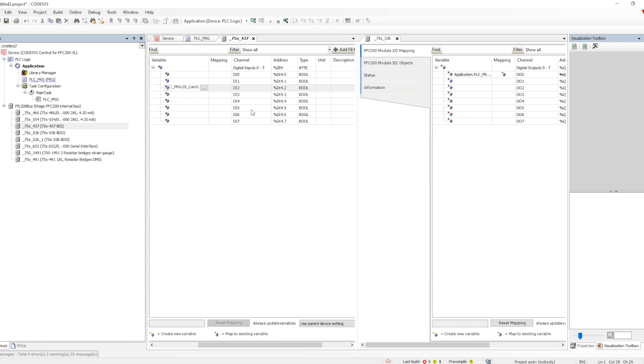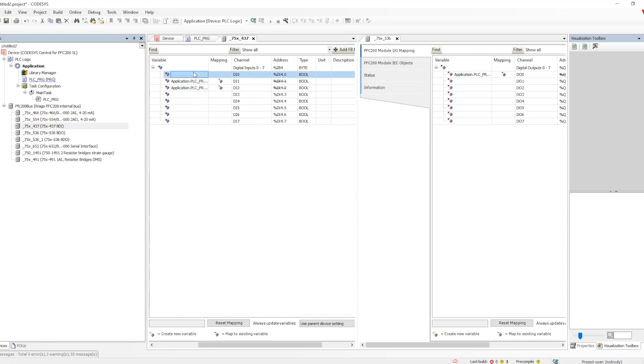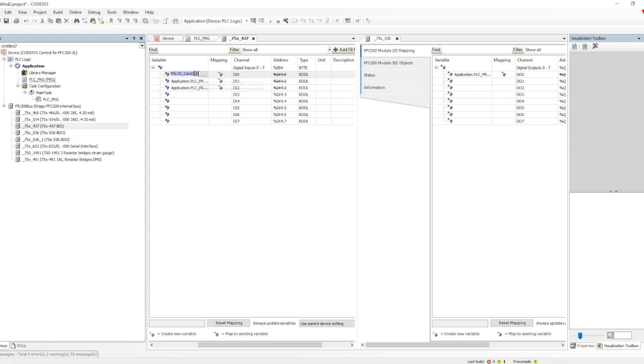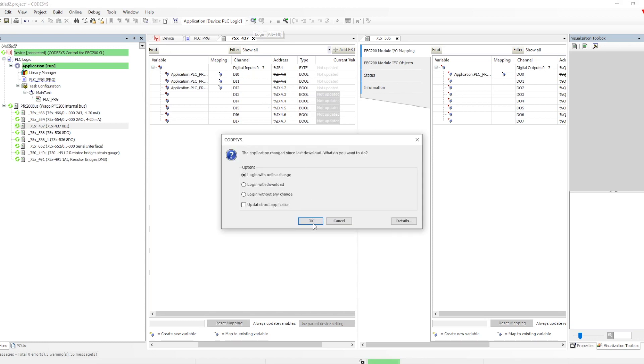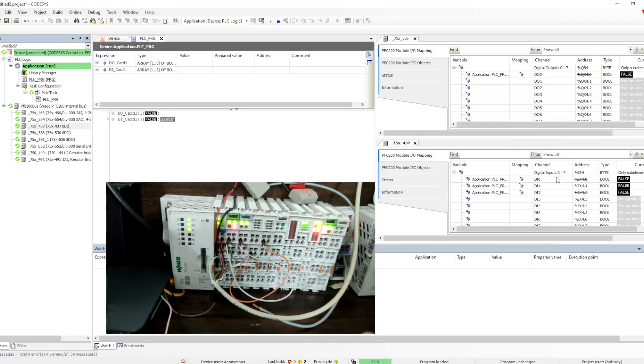Go to the application, browse, and then assign the array number. We can copy and paste it and only change the array number. Now we have connected everything — let's download the program. Now if you see, we have assigned three variables to three different channels and one output: three inputs and one output. Let me make it true. The input becomes true and DI3 also becomes true because of the loopback. If we make it false, everything becomes false and the IO channel also becomes false.